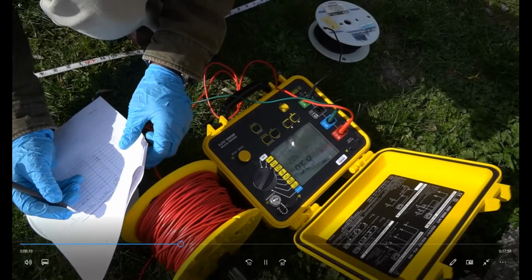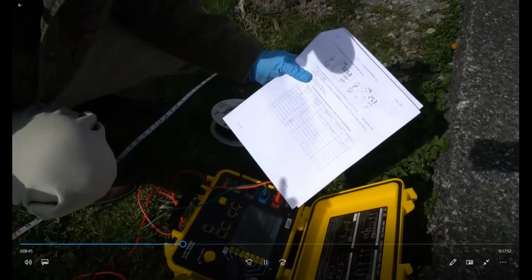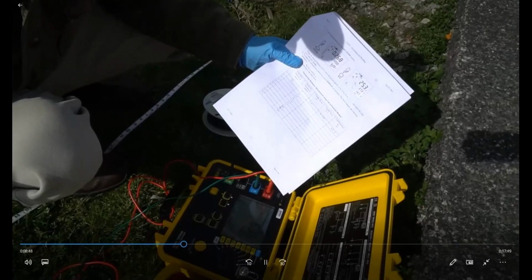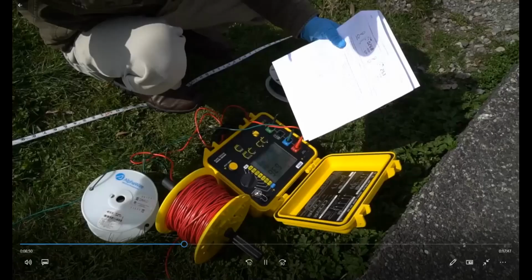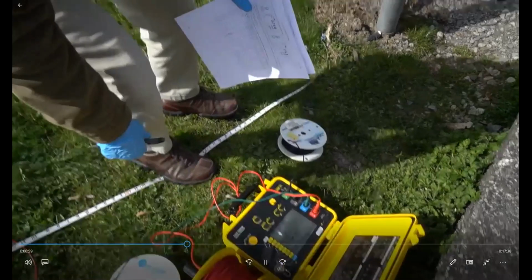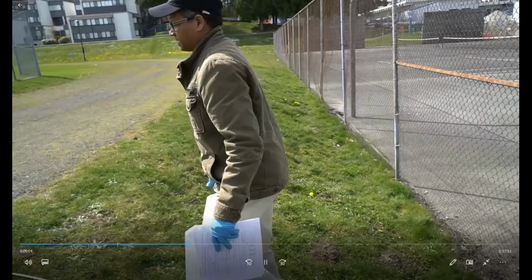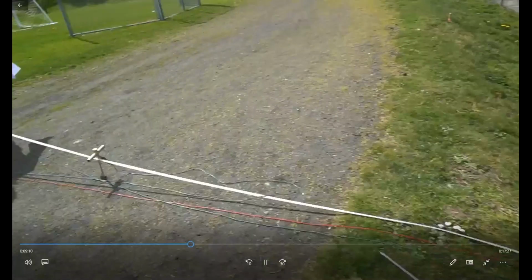Now what we'll do is change this distance D using the probe. We'll move it 5 meters away from the position it is at now, and then we'll change the distance here. The physical distance will change, and in the meter we will also change the distance, and we'll take the reading again. So let's see how we'll do that. Here we have 5 meters. We have to go now 10 meters from the ground grid.